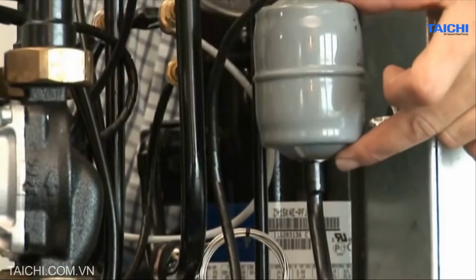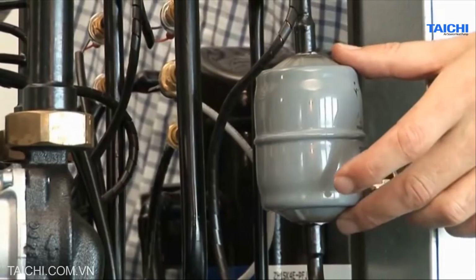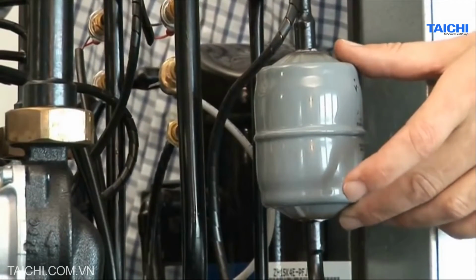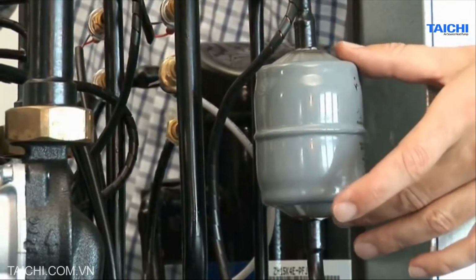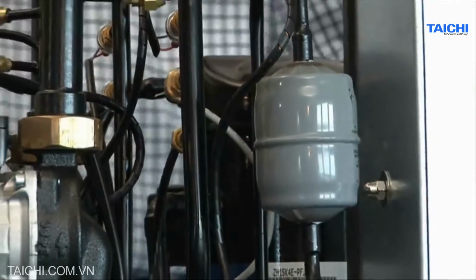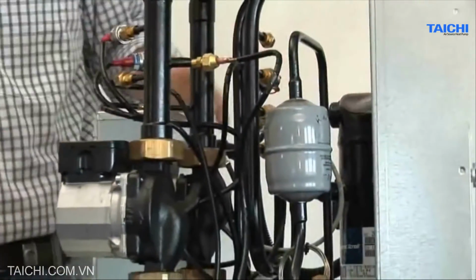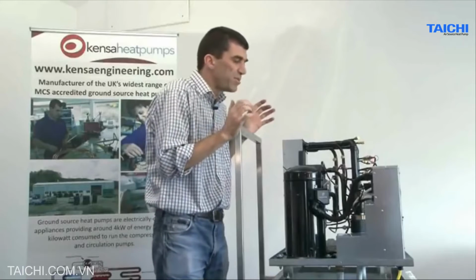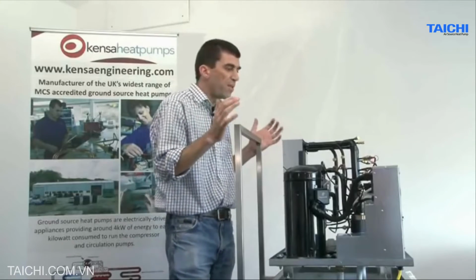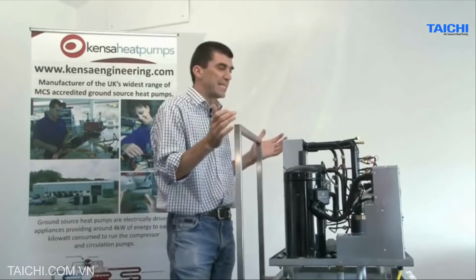Here is a filter dryer assembly. This keeps the refrigerant system clean and it removes any moisture that might have got in there during manufacture. And that, as the main components of the heat pump, is about it. The refrigerant never gets used up, it never wears out. In fact, the only thing that can go wrong with the refrigerant is it's leaked out.